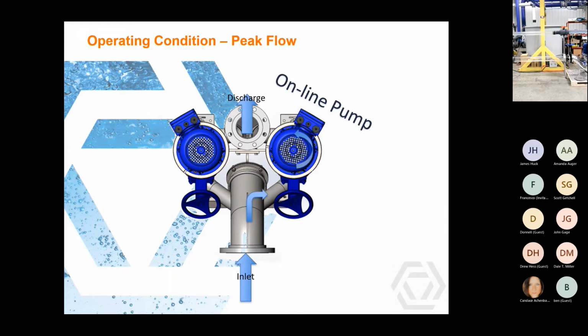The system can also detect when we're getting some peak flow scenarios. So that liquid level sensor, right? We set parameters of how we want the first pump to operate. If we know that the motor is running at 60 hertz and the liquid level is still increasing, then we know that we need to turn on the second pump. So the second pump comes on, manages the flow, and now we have two pumps managing the flow rate coming into the invert.